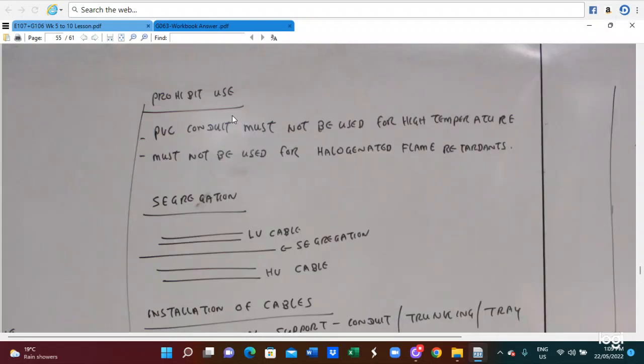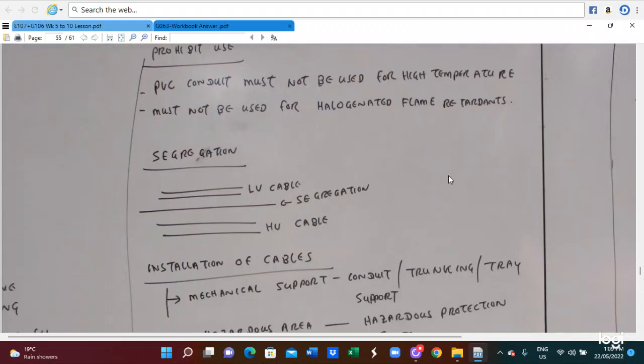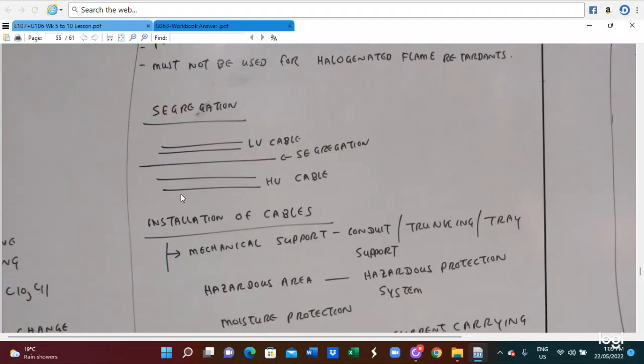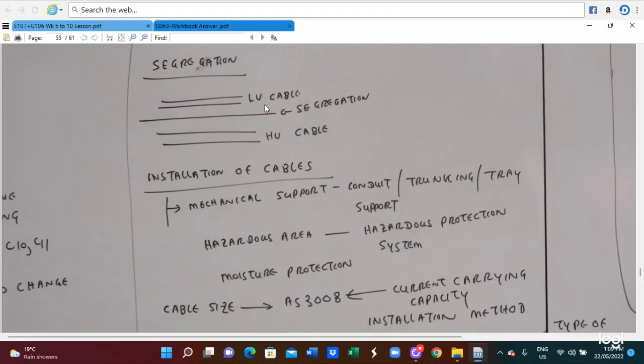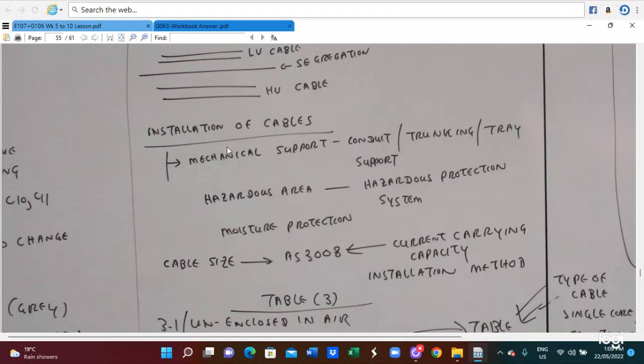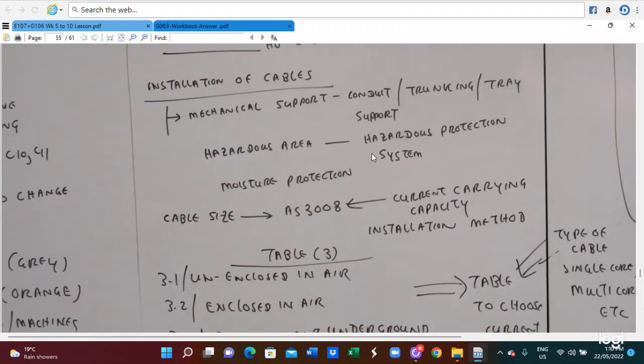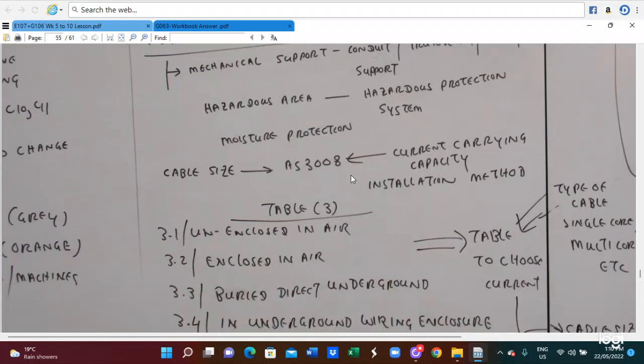So we have to observe the prohibited uses. PVC conduit must not be used for high temperature, and must not be used for halogenated flame retardants. Segregation: for every low voltage and high voltage connection, we have to use a segregation between the low voltage and high voltage cable. For installation of cable, we have to provide mechanical support for the conduit, trunking and tray support. For hazardous areas, we have to use a hazardous area protection system. For moisture protection, cable size, AS 3008 has to be utilized.